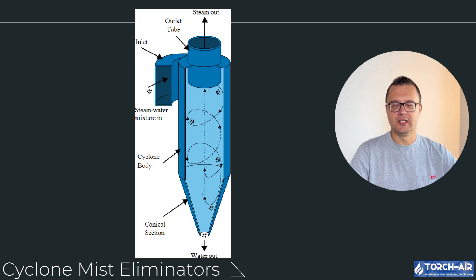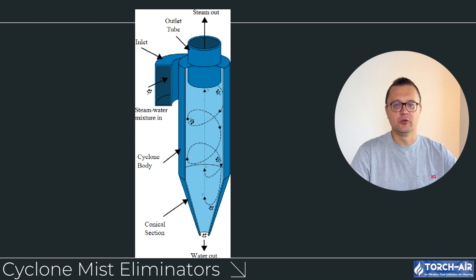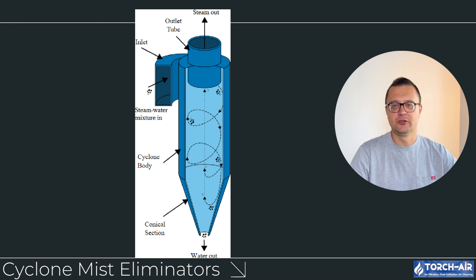Cyclone mist eliminators use centrifugal force to separate droplets from the gas stream. The gas enters the cyclone at high speed, causing it to spin. This spinning motion pushes the heavier liquid droplets to the outer walls, where they are collected and drained away. Best for high liquid loads and larger droplet sizes, cyclones are great for handling high flow rates and are relatively maintenance-free since they have no moving parts. However, they are less effective at capturing very fine mist, so they are often used as a pre-filter before more precise mist eliminators like mesh pads.